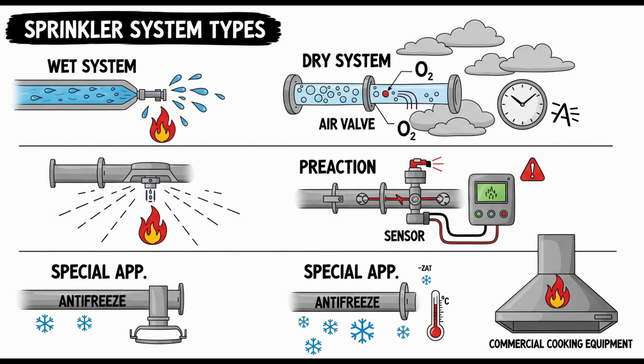Right, and here's where it gets really interesting. A specific requirement for wet pipe systems that use metallic pipe is that they need a single air vent. An air vent on a pipe full of water. That sounds counterintuitive. Why would you vent air out of a water pipe? It does, but think about how pipes are filled. Air can get trapped in high points or along horizontal runs, especially in metallic piping systems where you might have internal pipe wall irregularities. Okay, little pockets of air.